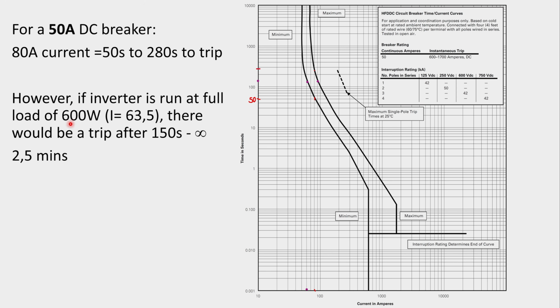So let's look at this. Normal load of 600 watts means the current is 63.5 amps coming from that battery. There's 20, 30, 40, 50, 60. I'll put a purple dot on it. So if I extend that line, here is the minimum. So it's about 150 seconds. But look at this. This line is in between the maximum and the minimum. So it might never ever trip.